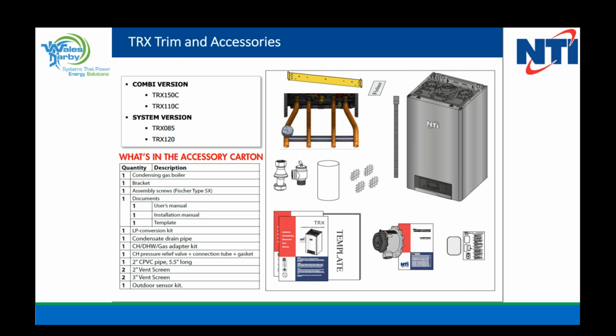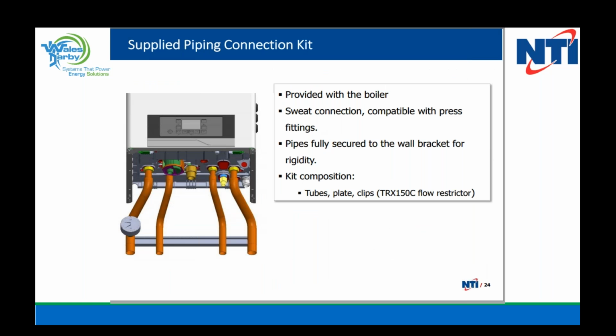So that outdoor sensor, if you want to make these boilers highly efficient, you want to make them sing, you want to use that outdoor sensor. If you don't, the boiler's just going to run at high, and then it's just a very expensive boiler, no different than cast iron. All right, John, going forward.